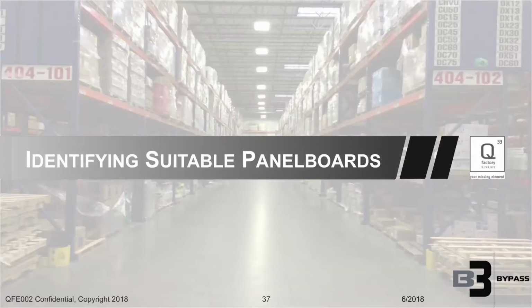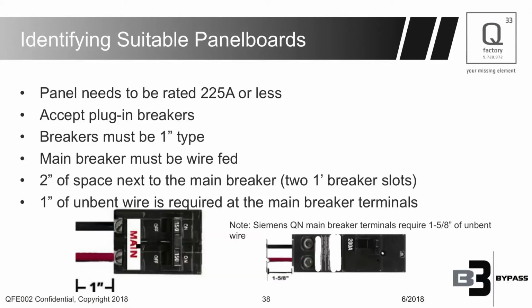Identifying suitable panel boards. Since we are considered a UL classified breaker, the maximum panel board we can be installed in is a 225 amp panel board or less. If you have a 400 amp panel board that has 2 200 amp main breakers, it cannot be installed. So this is a restriction by UL. It's a restriction that's part of the classified breaker program. So 100 amp, 115, 125 amp, 200 amp, 225 amp are all fine.